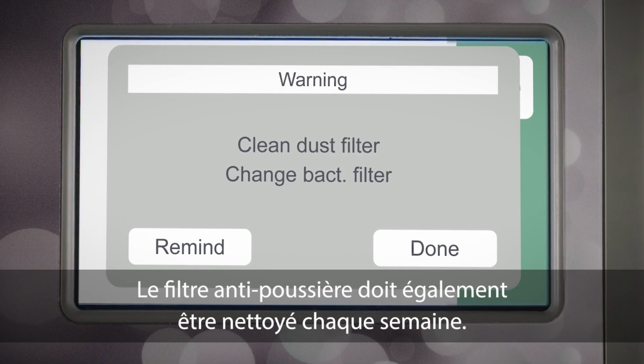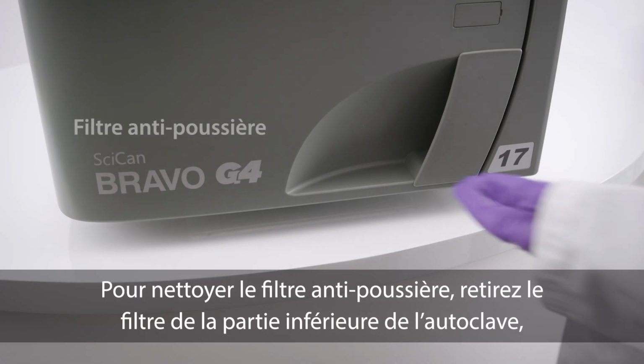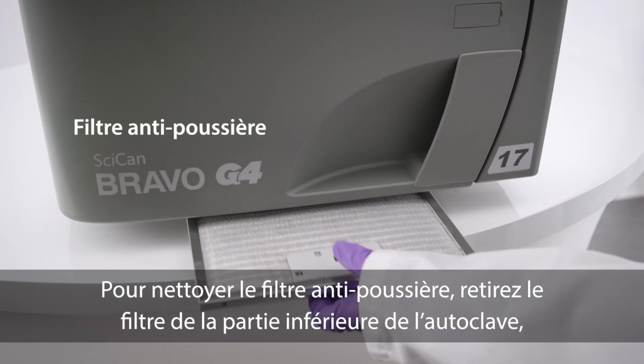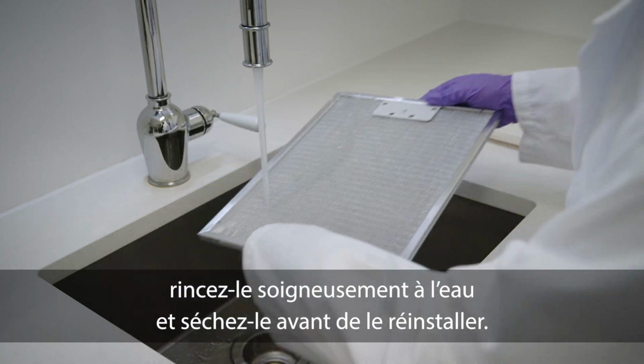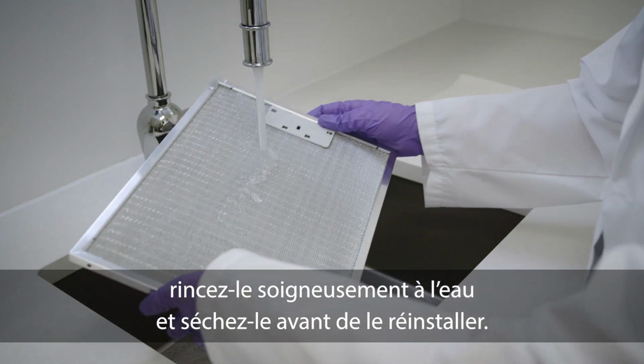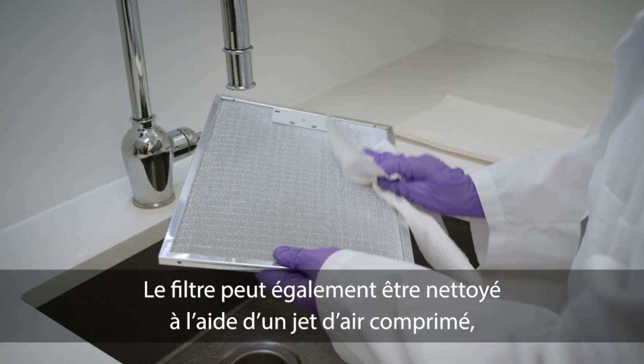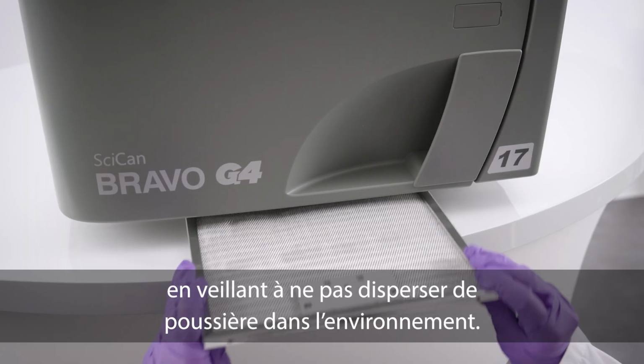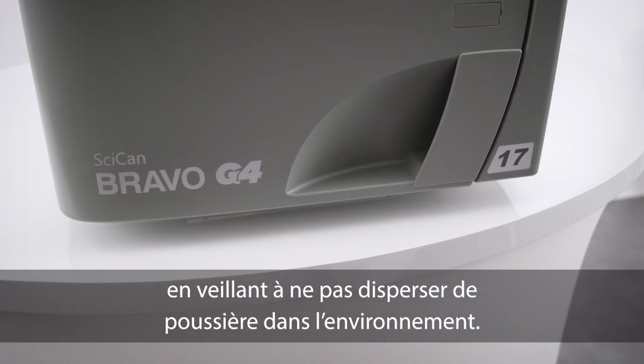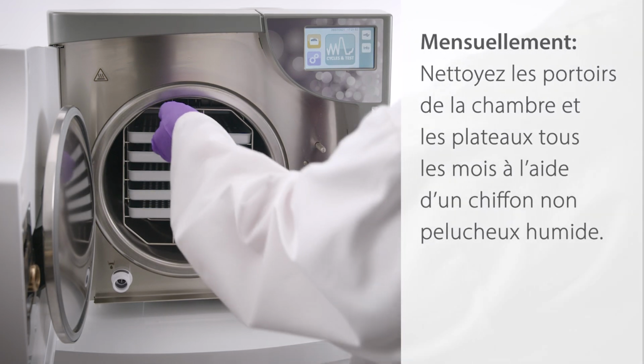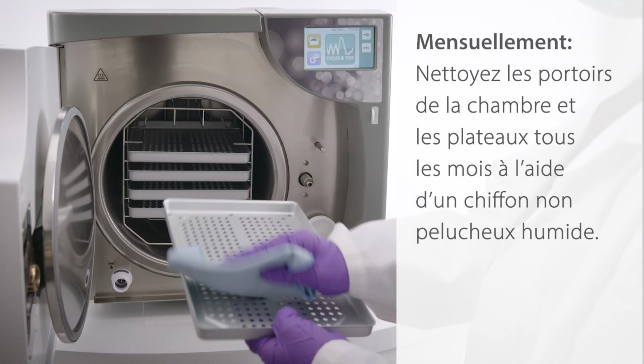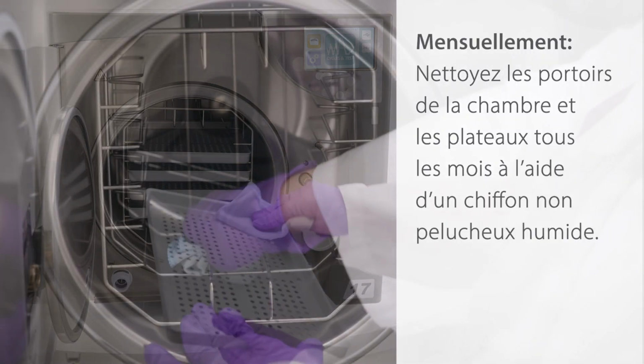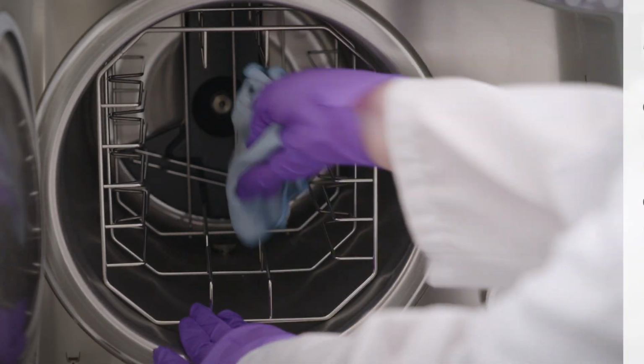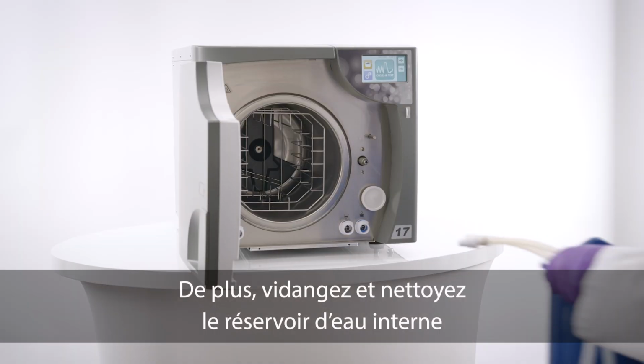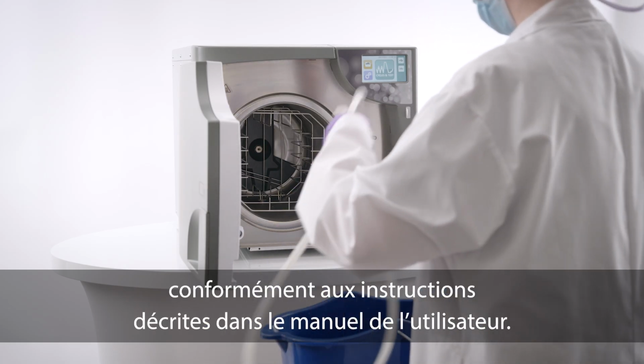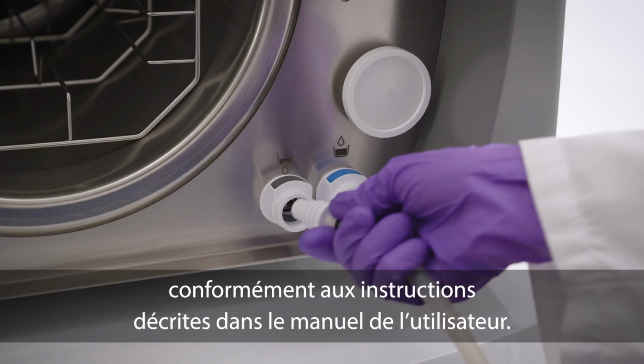The anti-dust filter should be cleaned weekly as well. To clean the anti-dust filter, remove the filter from the lower part of the autoclave, thoroughly rinse with water, and dry it before refitting. The filter can also be cleaned using a jet of compressed air, making sure not to disperse any dust into the environment. Monthly. Clean the chamber racks and trays every month with a lint-free, water-dampened cloth. As well, drain and clean the internal water reservoir as per the instructions outlined in the operator's manual.